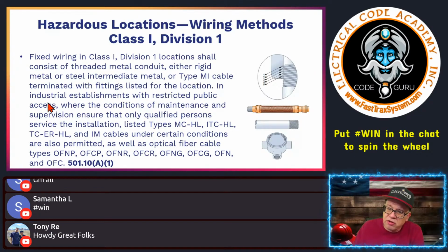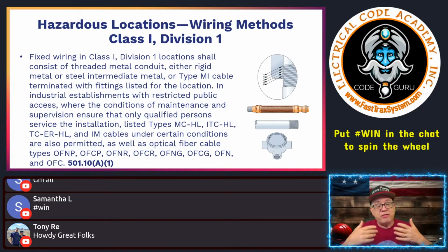It says in industrial establishments, so this is different. You have industrial establishments, and then you have other hazardous locations that may not be industrial establishments. And who determines what that is? What's an industrial establishment? Because we need to know that also in cable tray applications, right? When we can put single insulated conductors inside of a cable tray, it's only applicable to an industrial establishment. Who makes that decision? I would say the design professional, the local AHJ, building, zoning, all those types of things are going to make that decision.